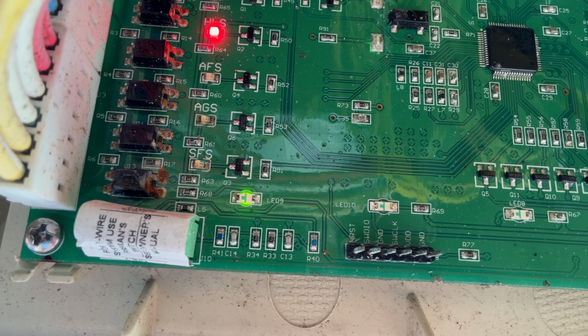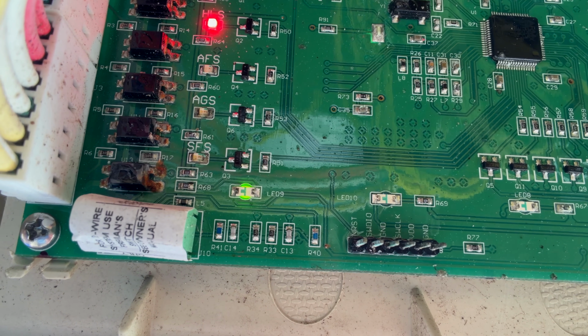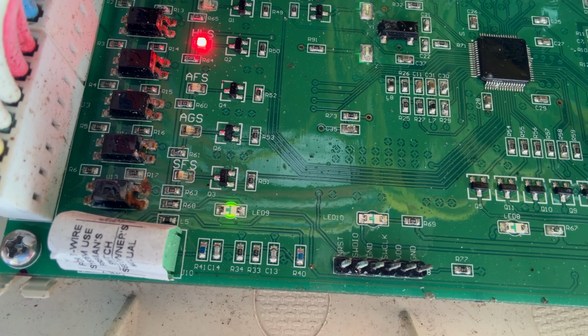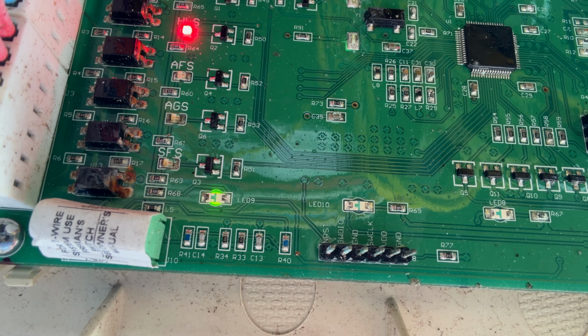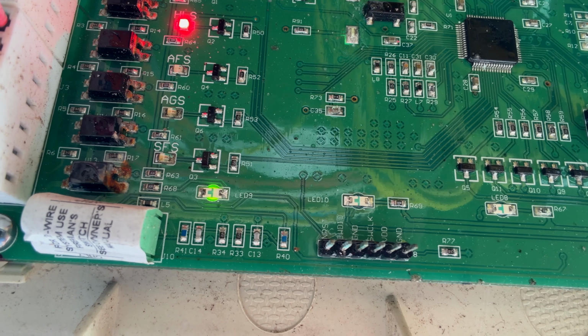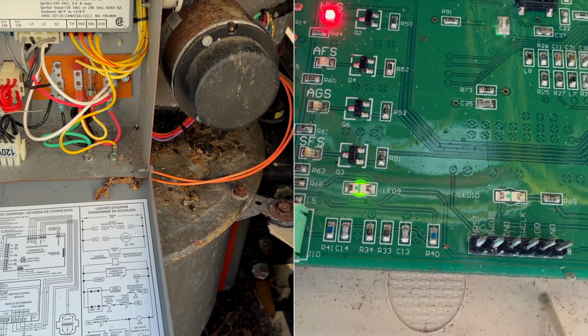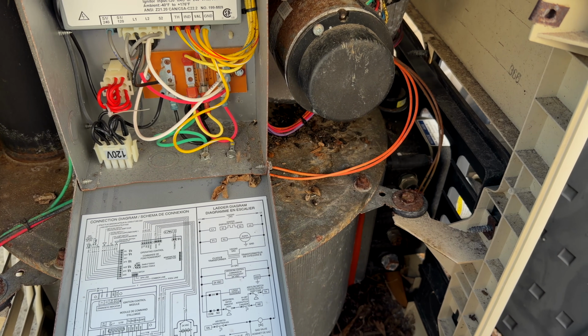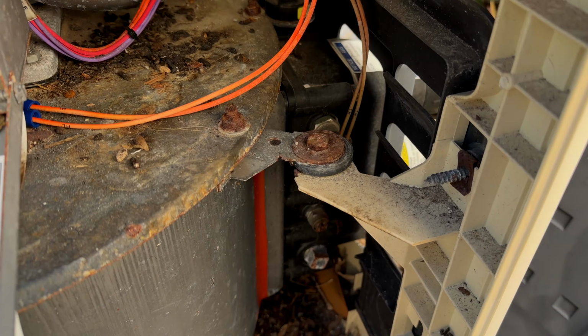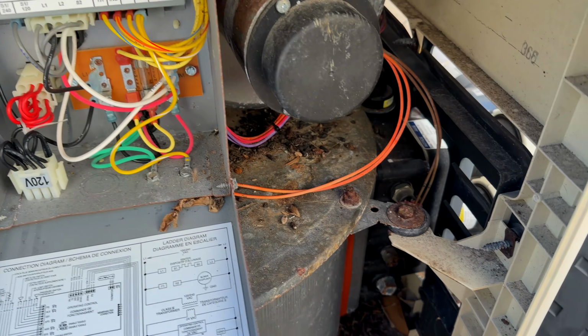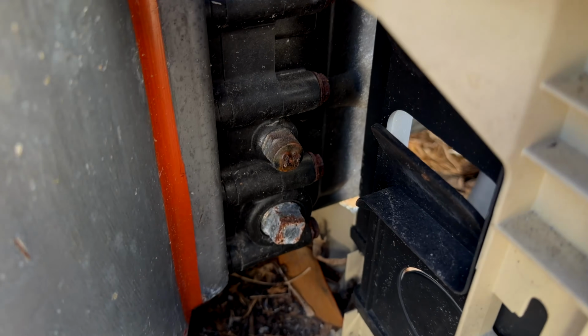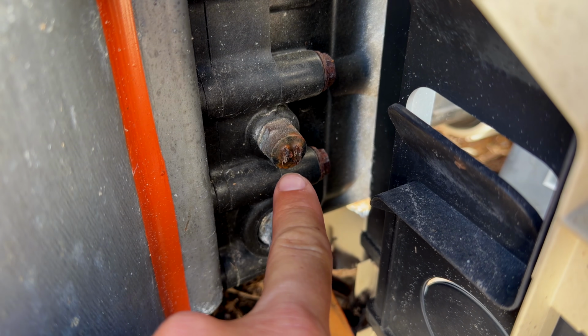So now what we need to do is locate the high limit switch and see what's going on, if there are any obvious issues there, and look at replacing that. But let me go ahead and show you where that is on this heater. So where is this high limit switch on this thing? Well, it's on this manifold here. It's on the same side as the electronics. And so if you look down here, it's this right here.